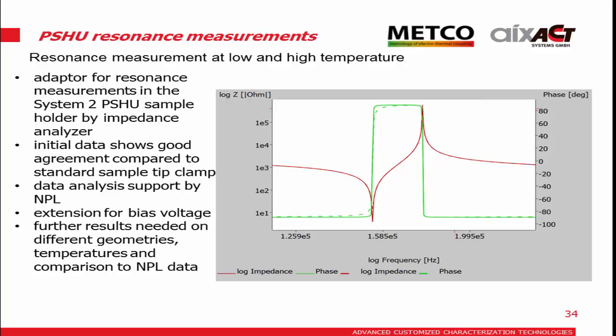And this is just one slide, the resonance measurements. So we did also some resonance measurements in the same sample holder, so that you can compare resonance and large signal measurements within one setup. And it nicely agrees with the free mounted sample and in the sample holder. But so far it's only for the in-plane modes, because the contacting will have an influence on your D33 in that case. So it's used for D31 and KP measurements.